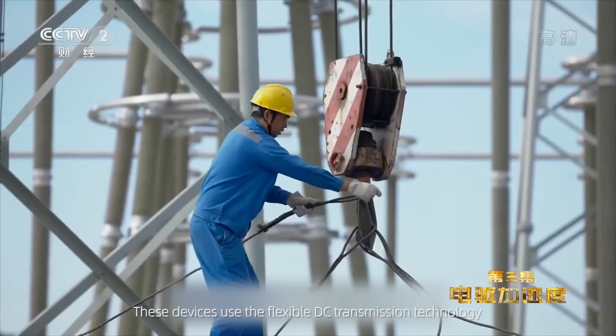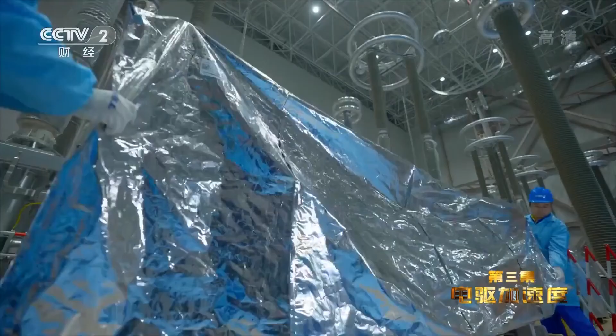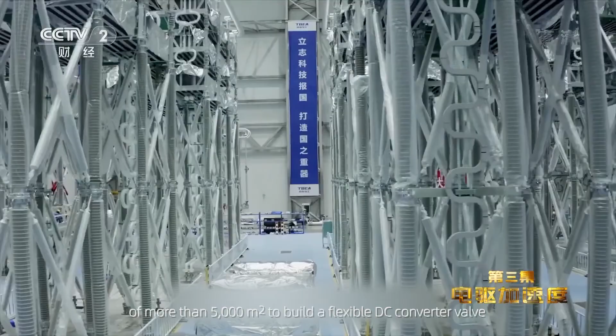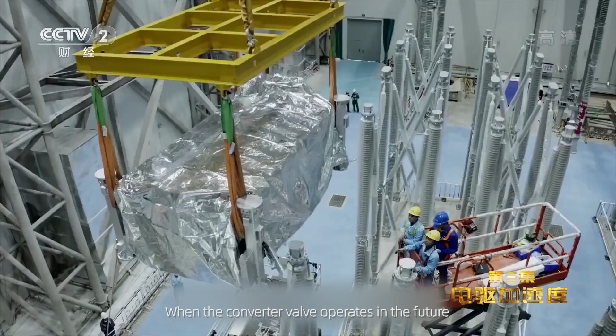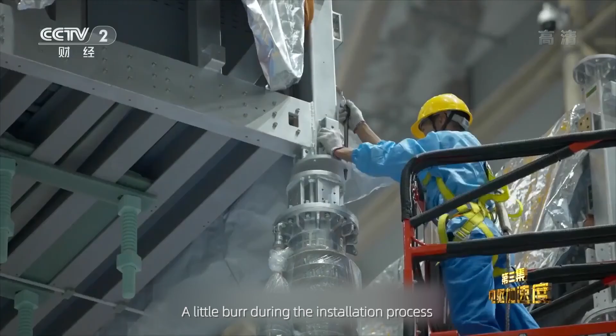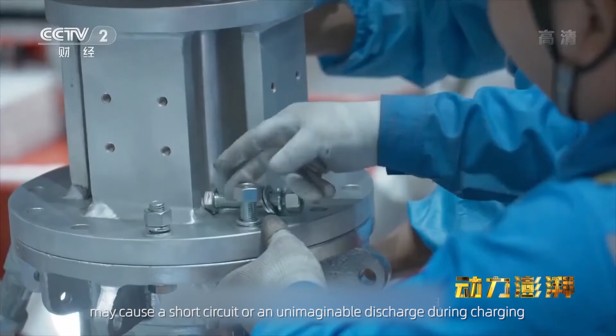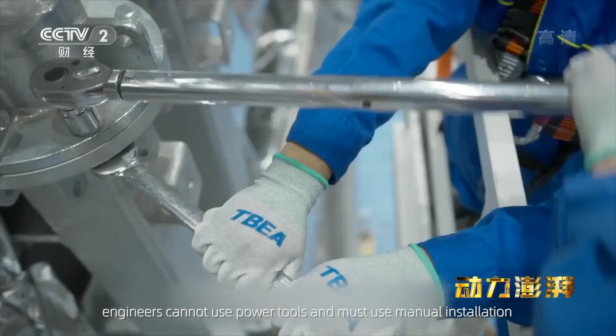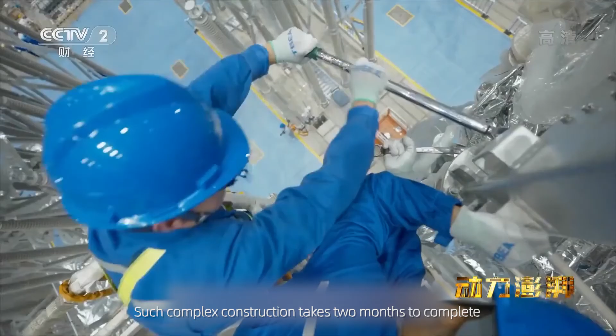These devices use the flexible DC transmission technology with the highest controllability in the world. And then, the workers will carefully assemble these precision equipment in the hall of more than 5,000 square meters to build a flexible DC converter valve with the highest voltage level in the world. When the converter valve operates in the future, the voltage is greater than 800 kilovolts. A little burr during the installation process, or even a little dust and iron filings on the surface may cause a short circuit or an unimaginable discharge during charging. Therefore, engineers cannot use power tools and must use manual installation. Such complex construction takes 2 months to complete, even if the experienced engineers work together.